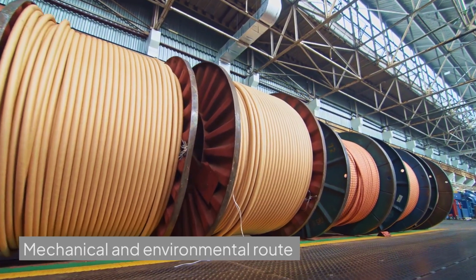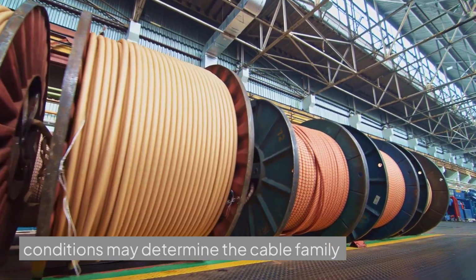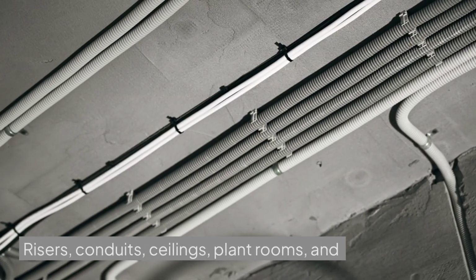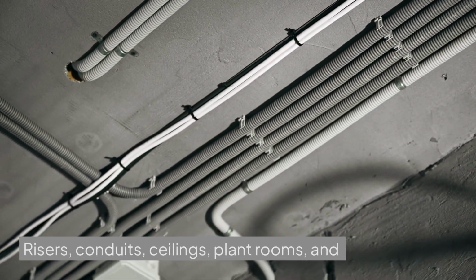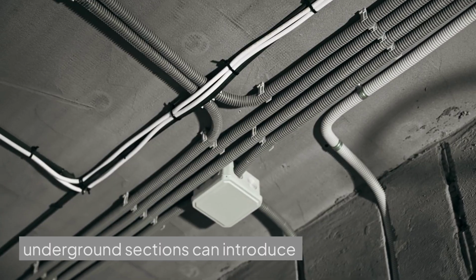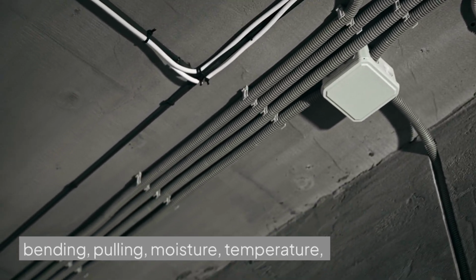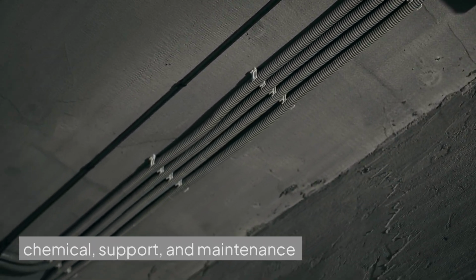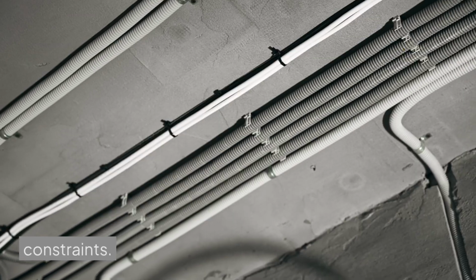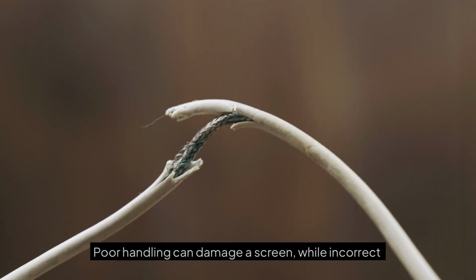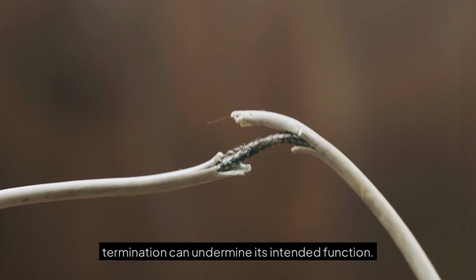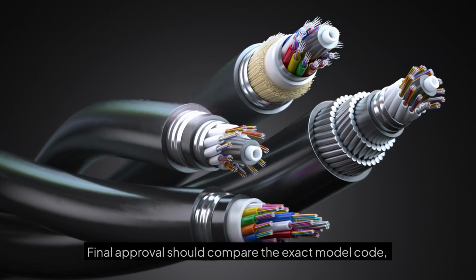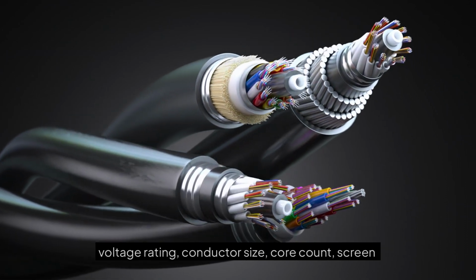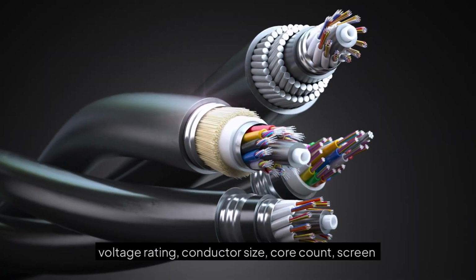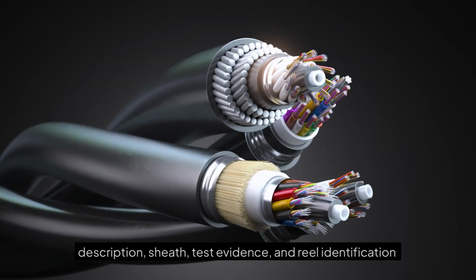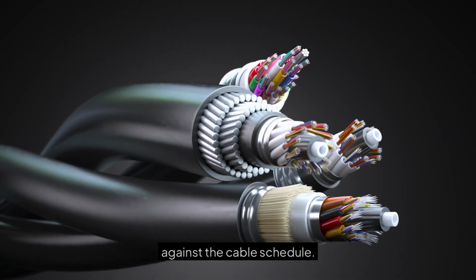Mechanical and environmental route conditions may determine the cable family before screening is considered. Risers, conduits, ceilings, plant rooms, and underground sections can introduce bending, pulling, moisture, temperature, chemical, support, and maintenance constraints. Poor handling can damage a screen, while incorrect termination can undermine its intended function. Final approval should compare the exact model code, voltage rating, conductor size, core count, screen description, sheath, test evidence, and real identification against the cable schedule.